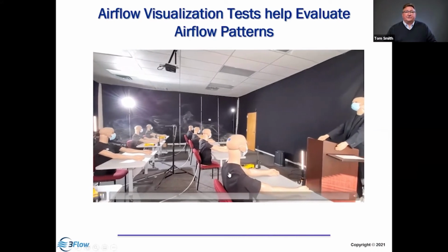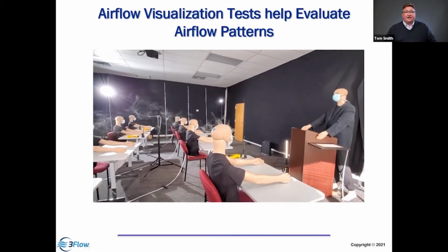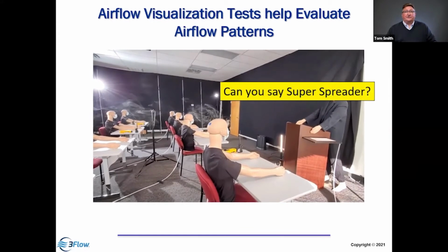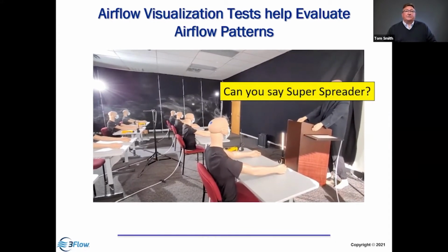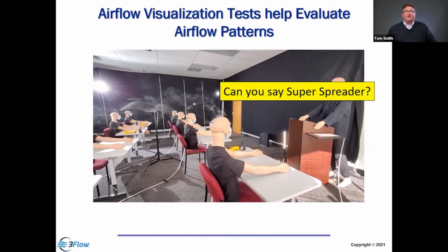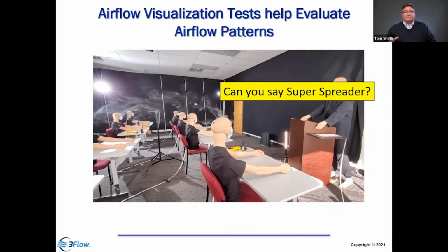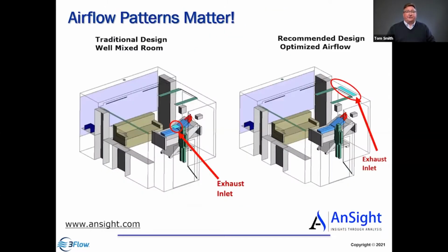And so if this was an infected person, we'd anticipate that we may have what we call a super spreader event, right? So we want to avoid this type of airflow motion in the space, and we can use the HVAC system, the supply diffusers, and the exhaust to provide more effective airflow patterns, and that's what we call ventilation effectiveness. So we're going to talk in detail about lab design and how we use the airflow within the lab to help reduce concentrations and support the performance of the fume hood.